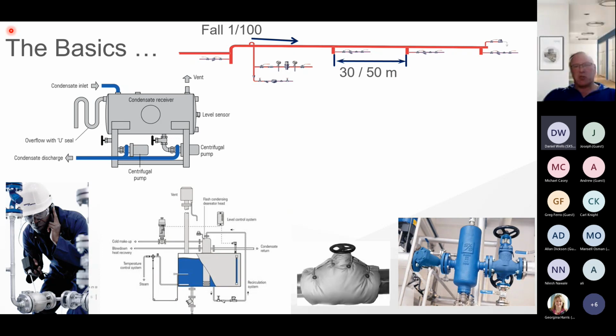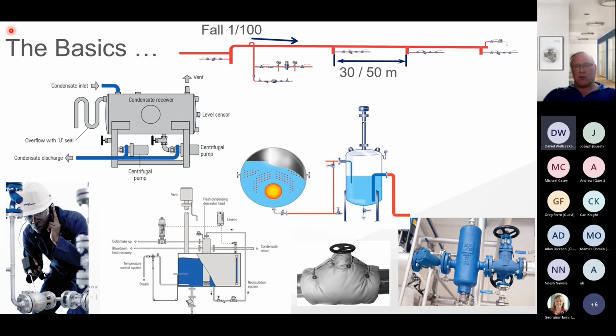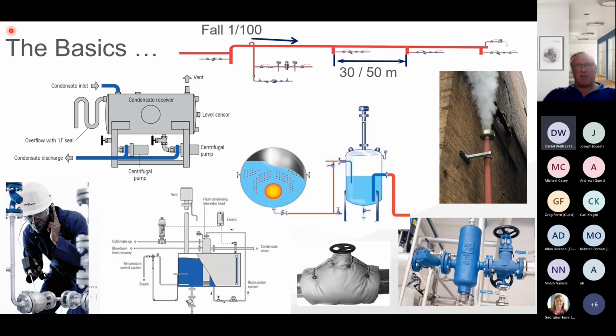Reducing heat losses in the infrastructure with adequate insulation. Reducing the heat losses, we're reducing steam demand. Therefore, we're operating with a greater degree of efficiency. The boiler blowdown controls, we want to make sure that they're automated wherever possible. If we've got manually operated blowdown controls, it's nigh on impossible to understand the amount of hot water we're putting to waste. And then we also want to keep an eye on those flash steam vents. Well, remember, there's just as much energy in that flash steam as there is in plant steam.